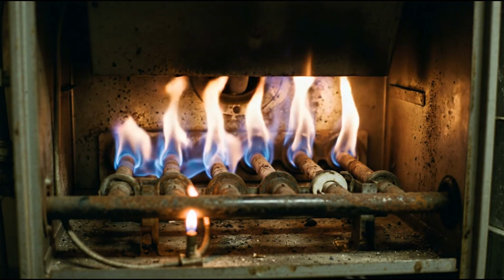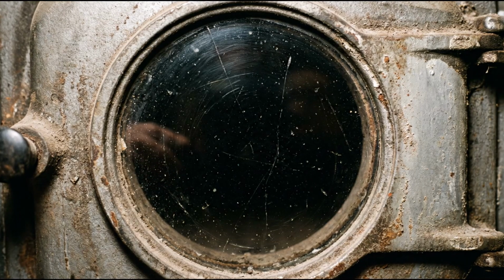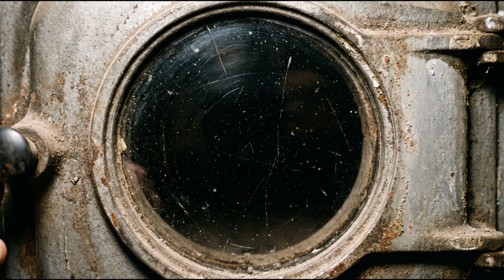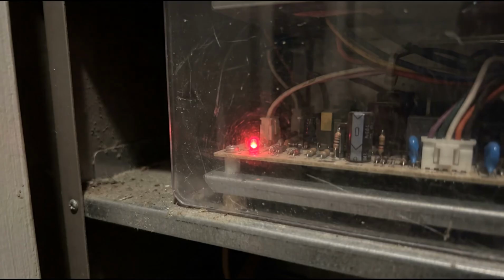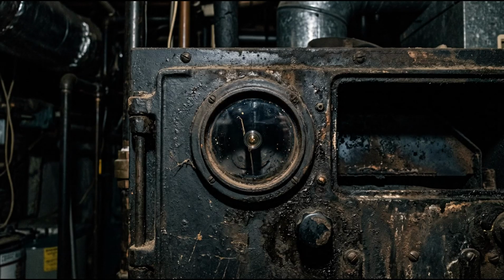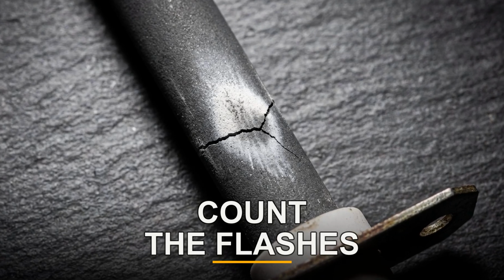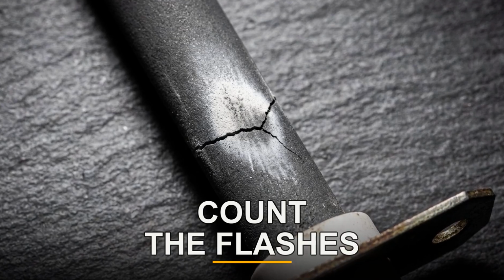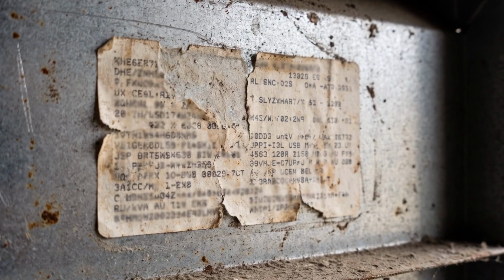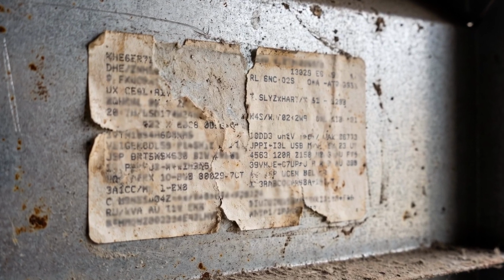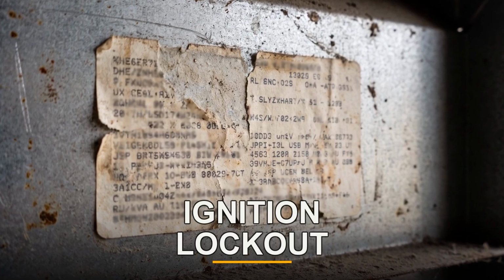If you hear the inducer run and you never see that orange glow and then everything shuts down, that is your igniter 9 times out of 10. Many furnaces will also blink an error code at you through that same window. Count the flashes and check the legend printed inside the door panel. A code for ignition failure or ignition lockout points the same direction.